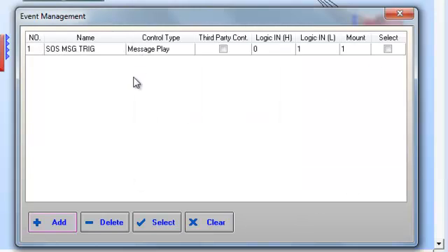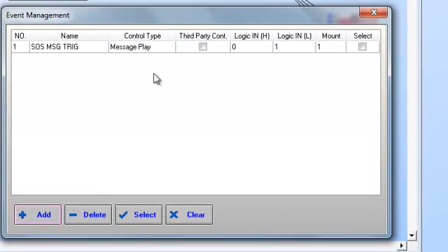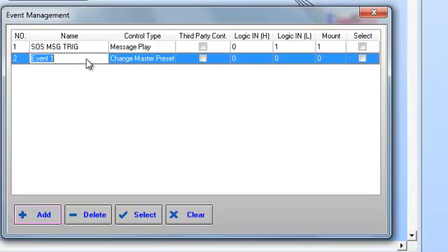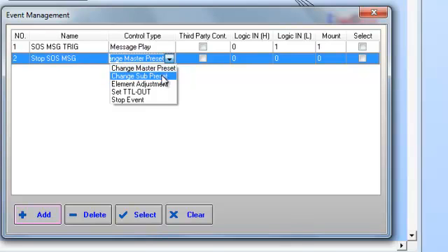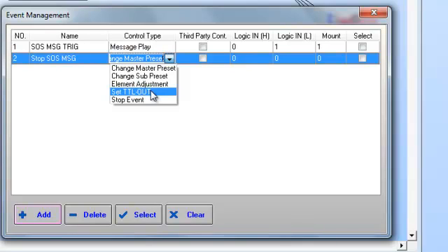I can even view the assigned message here and change it if I want. Remember, this is set to play continuously because in the message player we set it to play forever. So what happens when the contact for control input number 1 is released or opened back up? We need to tell it: when this happens, stop playing the message. We do that by adding another event called 'Stop SOS Message.' The control type options include changing master presets, sub presets, element adjustments like selector switches, or a control output device.